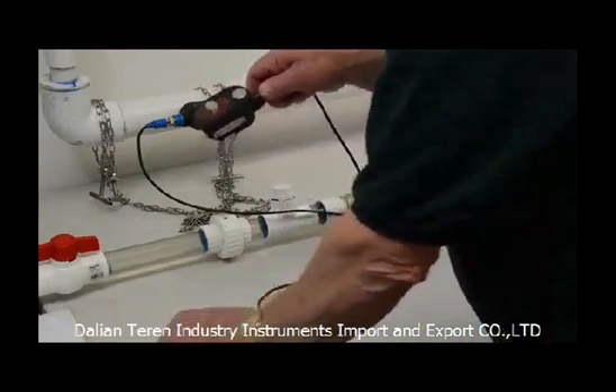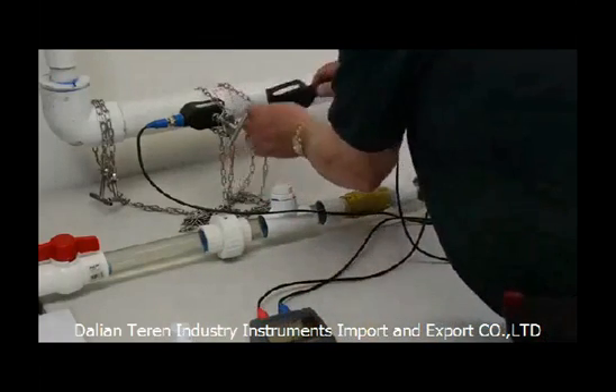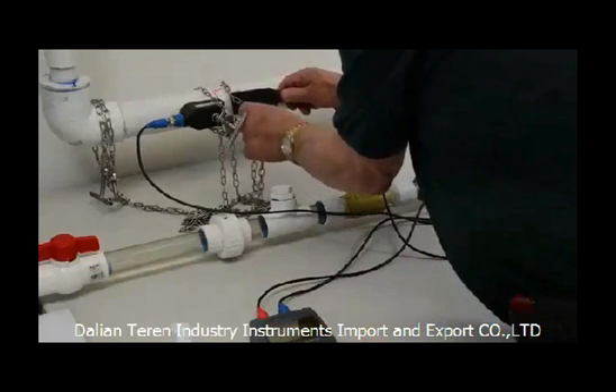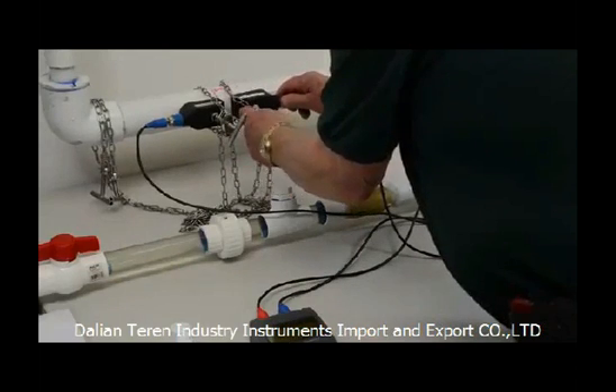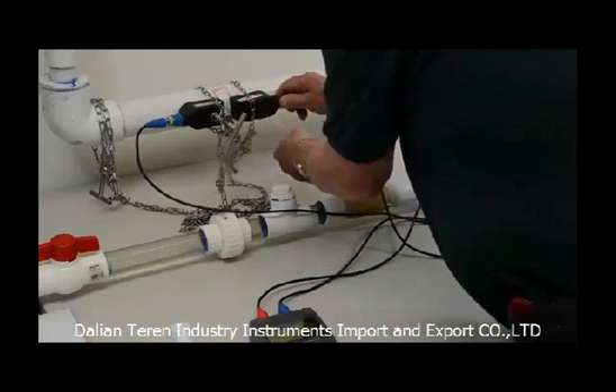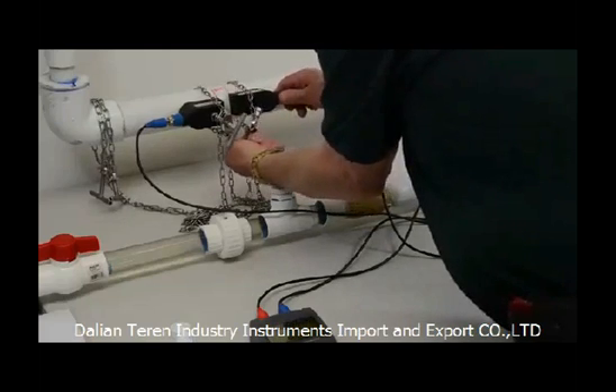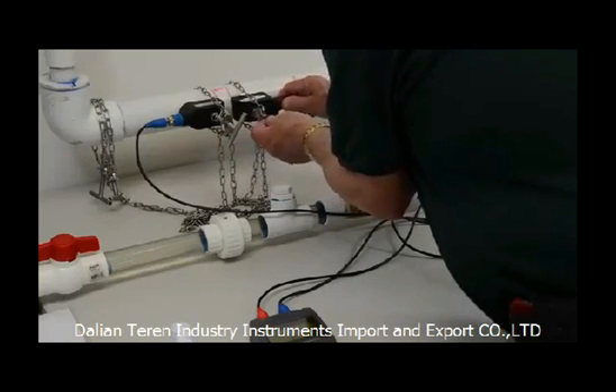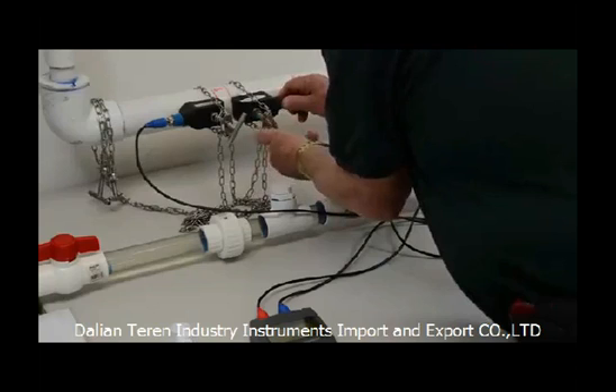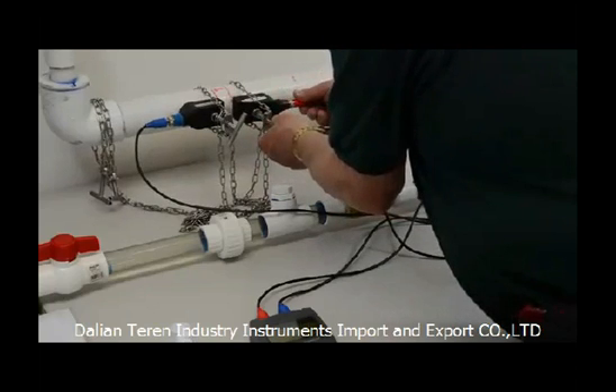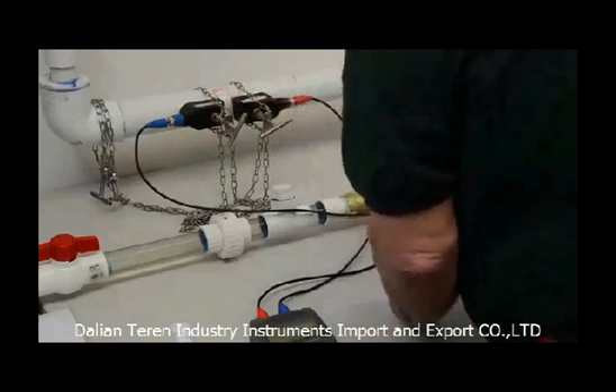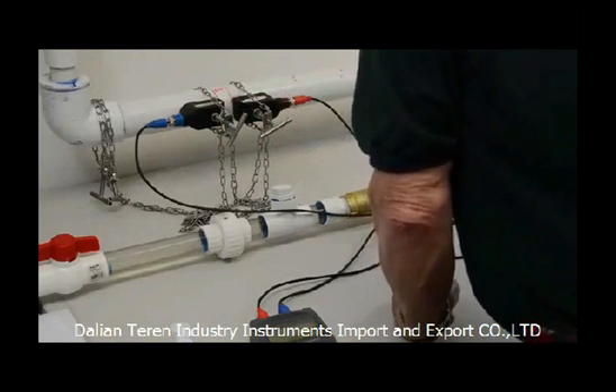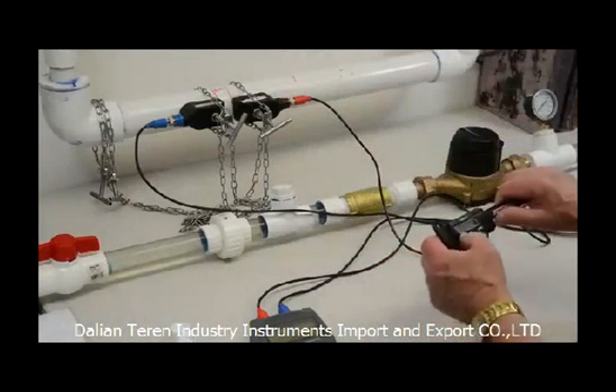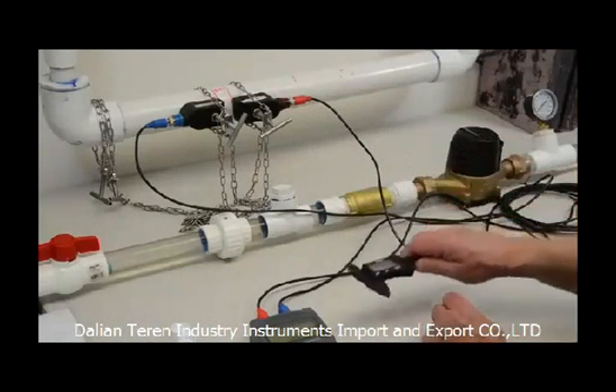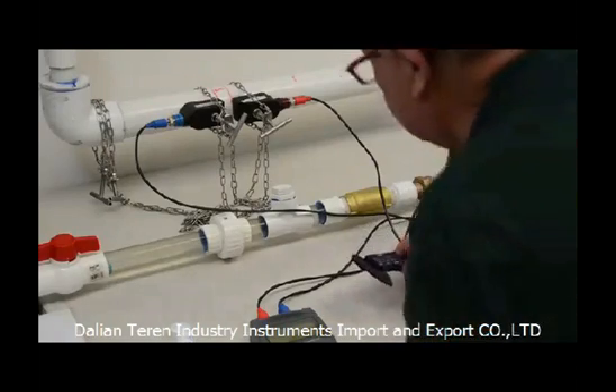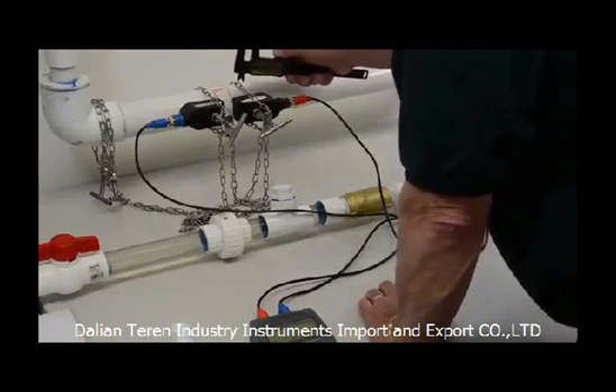And you can see I don't move it all around. I just want to get a good dollop on there. And I'll hook it up here, put my cable clamps on, and you can clamp these on in a number of different methods. We're just using the cable clamps that come in the kit, and you could use zip ties, you can use anything you want. Okay, so I've just got these transducers mounted. Now I'm going to measure to see that I'm going to be at my proper spacing, which is 0.91 inches. This spacing is important for accuracy.